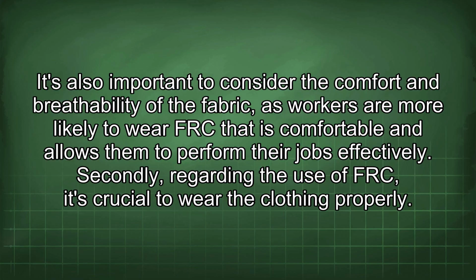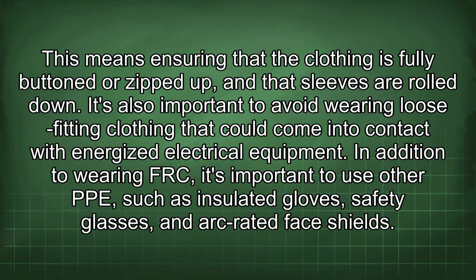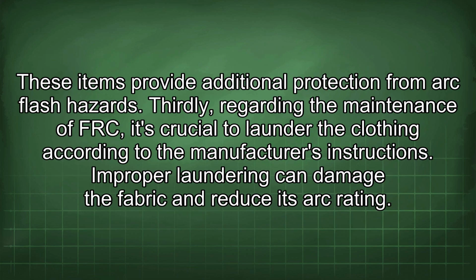Secondly, regarding the use of FRC, it's crucial to wear the clothing properly. This means ensuring that the clothing is fully buttoned or zipped up and that sleeves are rolled down. It's also important to avoid wearing loose-fitting clothing that could come into contact with energized electrical equipment. In addition to wearing FRC, it's important to use other PPE such as insulated gloves, safety glasses, and arc-rated face shields. These items provide additional protection from arc flash hazards.